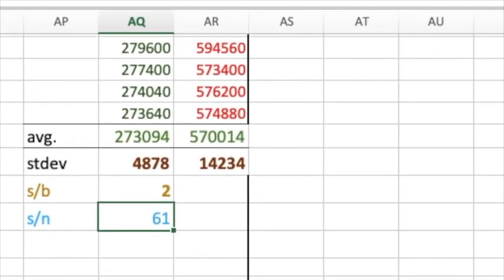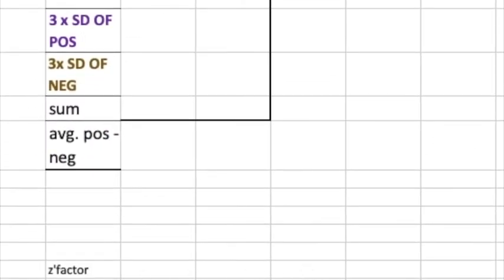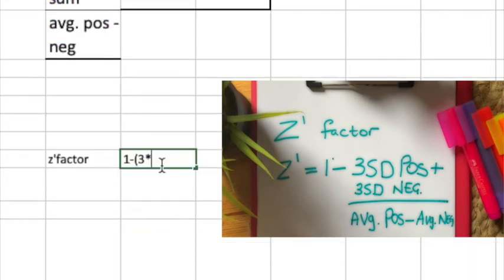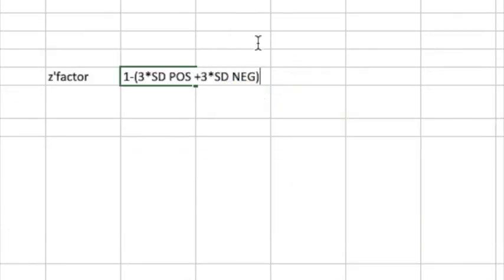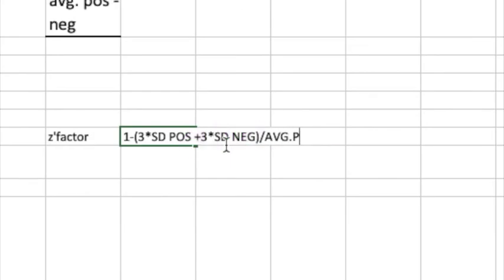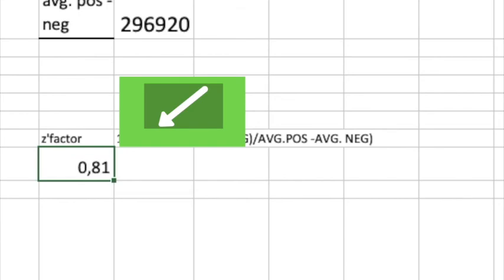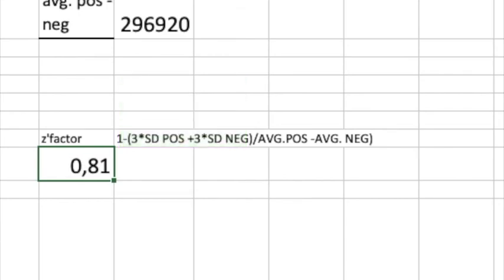How does that affect our Z prime factor? The Z prime factor is one minus three times the standard deviation of the positive, added to three times the standard deviation of the negative, divided by the average positive signal minus the average negative signal. Look at that — the same signal to background of just 2, but because we have really tight variability, it's 0.81. How good is that? That is great.